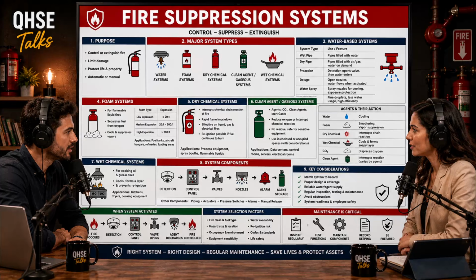And there are two main categories of heat detectors: fixed temperature and rate of rise. Yes. A fixed temperature detector operates when the ambient temperature reaches a specific point, say 135 degrees Fahrenheit. It doesn't care how long it takes to get there. But wait, if I have a massive warehouse with really high ceilings, a fire might have to get dangerously large before the ceiling temperature hits 135 degrees, right? Yeah, and that is the inherent weakness of fixed temperature detectors. They suffer from something called thermal lag. By the time the metal inside the detector actually absorbs enough heat to reach 135 degrees, the air around it might already be 160 degrees, and the fire below is huge.